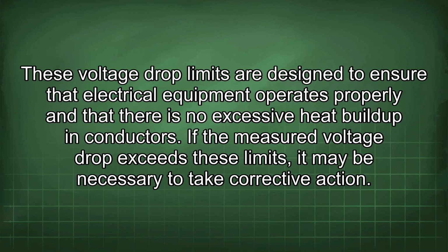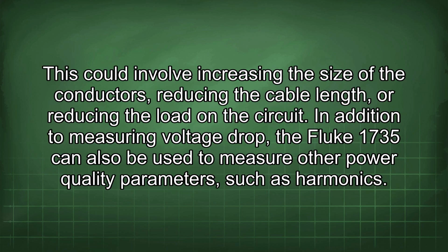These voltage drop limits are designed to ensure that electrical equipment operates properly and that there is no excessive heat buildup in conductors. If the measured voltage drop exceeds these limits, it may be necessary to take corrective action. This could involve increasing the size of the conductors, reducing the cable length, or reducing the load on the circuit.